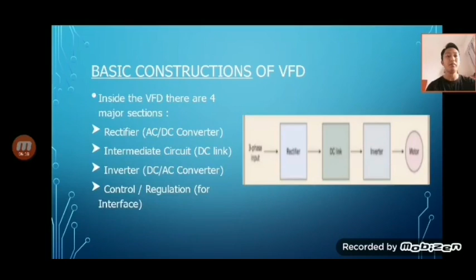So this is the basic working of the VFD. The power first goes to the rectifier, where 3-phase AC is converted into a rippling DC voltage. Then the intermediate circuit smoothes and holds the DC voltage at a constant level, as an energy source for the inverter. Then the inverter uses DC voltage to drive the motor with varying levels of voltage and current depending upon the control circuits, usually a set of 6 IGBTs. The control section uses the frequency, voltage, and phase angle to control the inverter. So how much frequency we use is controlled by the control section.